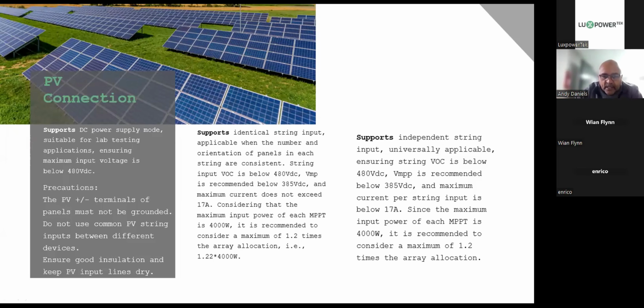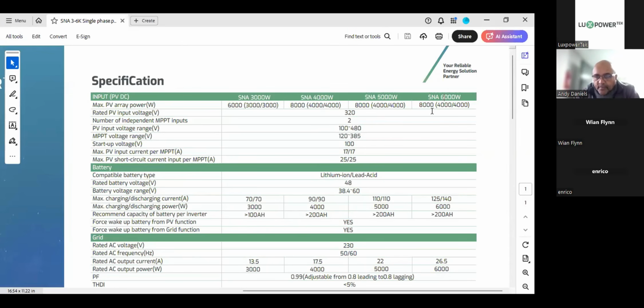So remember, let's go here to the spec sheet for the SNA, and here we have the 6 kilowatt. If you have a look here, the maximum PV array power is 8 kilowatts. That's the maximum that the MPPT can take. Remember, our machine has 2 inputs, so that'll be 4 kilowatts per input. When we say we have 3 criteria to meet, it's these: you cannot exceed 4 kilowatts per input, you cannot exceed the voltage input, and you cannot exceed the current input.